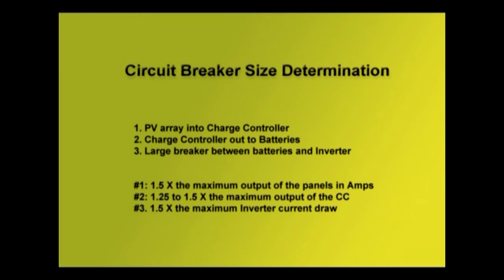Now, what I'm going to say in the next 2 minutes is extremely important. It's priority 1, so take notes on this. The circuit breaker size determination. We've got 3 main breakers in there. Number 1, the photovoltaic array coming into the charge controller. We're going to put a breaker in there so we can turn it off and protect that circuit. Number 2, out of that charge controller, the output goes to the batteries to charge the batteries. That's where our number 2 breaker is going to go in. These are our 2 smaller breakers. They can go in the same housing, but they're both smaller breakers.